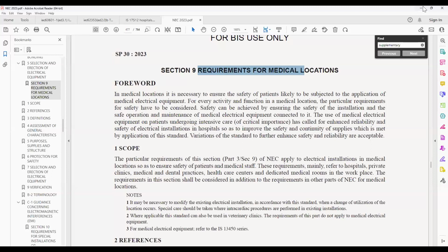So basically, during the first fault, your supply should not trip in a medical location group 2 location. So such additional safety measures are very much included in the standard. An example I am showing; the serial numbers 1 to 5 are not the entire safety measure, but just an example. Medical locations are classified into group 0, group 1, group 2 locations. TN-S system or IT system may be required depending upon the criticality. Protective equipotential bonding, 50 volt in group 0 location, 25 volt in group 1 and group 2 locations are necessary.